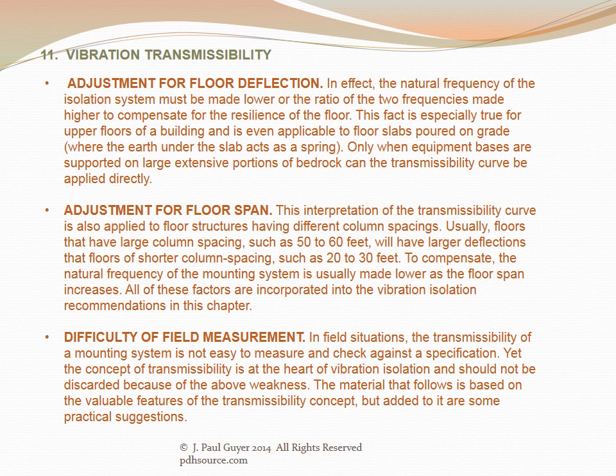The natural frequency of the isolation system must be made lower — or the ratio of driving to natural frequency made higher — to compensate for floor resilience. This is especially true for upper floors and floor slabs poured on grade where the earth acts as a spring. Floors with large column spacing (50–60 feet) have larger deflections than those with shorter spacing (20–30 feet). Consequently, the natural frequency of the mounting system is usually made lower as floor span increases, and all these factors are incorporated into the vibration isolation recommendations.